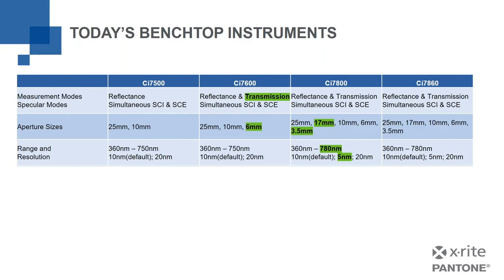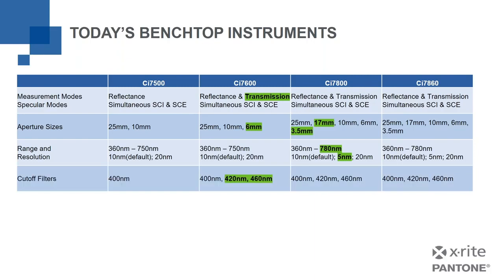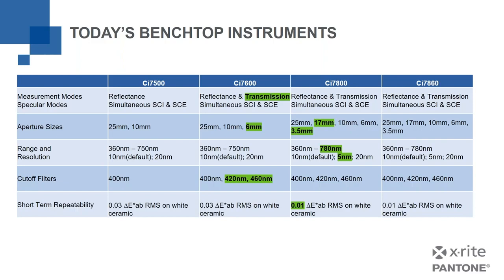Now, depending on what you're measuring and your requirements, you may need those kinds of things. Cutoff filters, which are used for UV measurements and UV calibration, and see what's available. The short-term repeatability, this is how you test an instrument repeatably measuring the same thing. You can see on the right-hand side, those two devices, the higher-end devices, if you will, go down to a 0.01 versus a 0.03 for the two on the left.